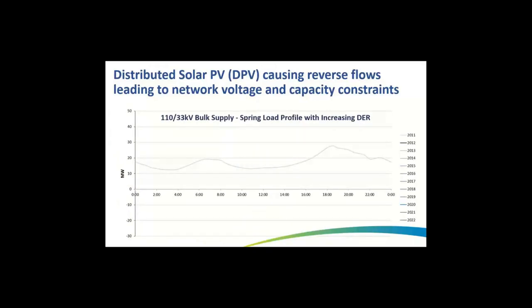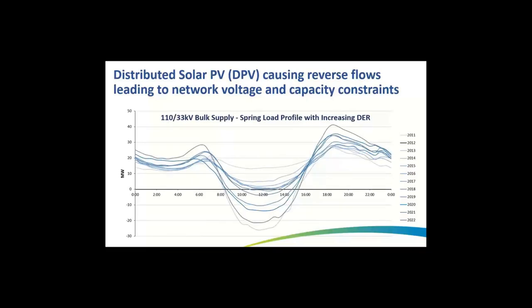The result of this is that we're increasingly seeing reverse flows. This is one particular substation supplied from the transmission operator, Powerlink, in Queensland. And you can see over the last decade, those flows have not only reduced during the middle of the day, but have now reversed significantly as the PV in the distribution network flows back into the transmission network. And this has led to both voltage and capacity constraints on the distribution network.